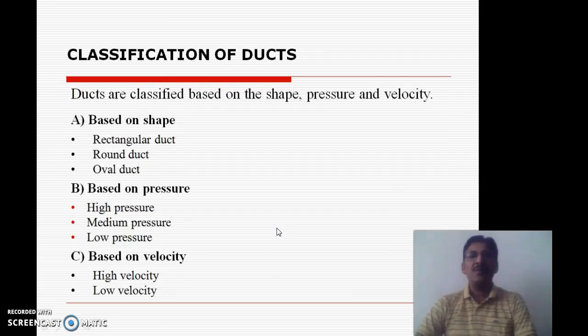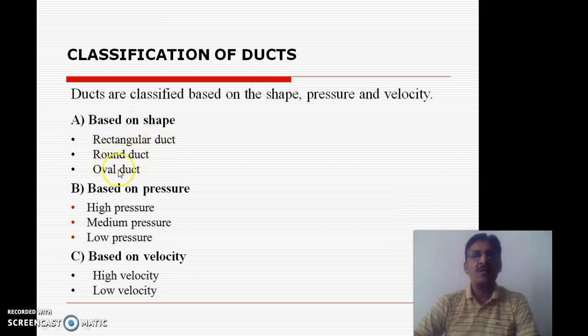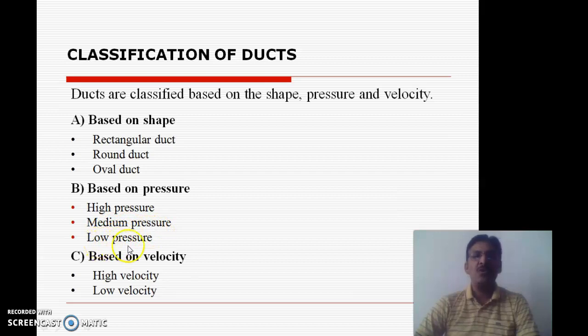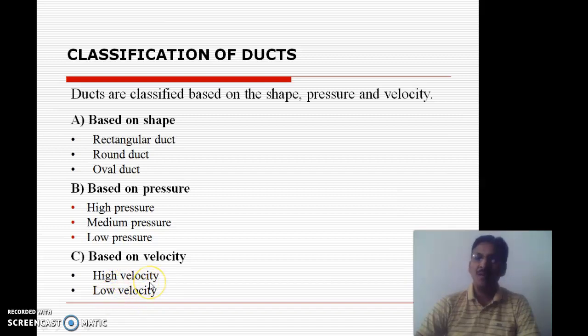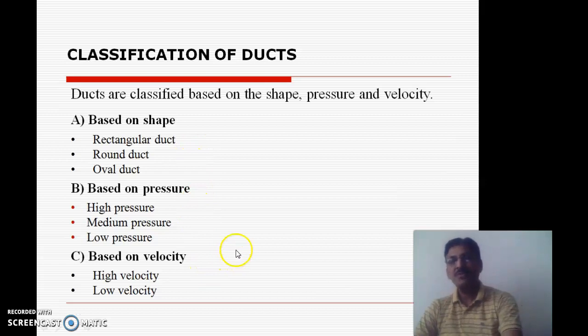There are different types of ducts generally used for air distribution systems. The classification of ducts is based on shape, pressure, and velocity. Based on shape: rectangular ducts, round ducts, and oval ducts. Based on pressure: high pressure duct, medium pressure duct, and low pressure duct. Based on velocity: high velocity and low velocity. When the velocity of air is higher than 10 meters per second, it is a high velocity duct. When the velocity is less than 10 meters per second, it is a low velocity duct.